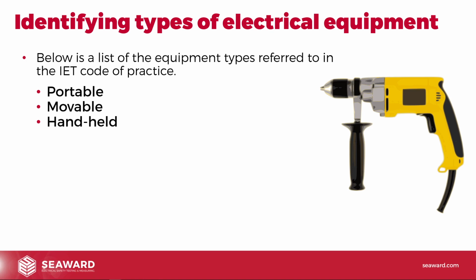Now, one that is seen as high risk, and a typical example here on the slide you can see the hand drill, is handheld equipment. Handheld equipment is really what you'd class as portable equipment, but handheld equipment is equipment that's designed to be held in your hand during normal use. Now, the problem with this is, where's it going to be when it goes wrong? In your hand. So the likelihood of somebody getting an electric shock if this piece of equipment goes wrong is a lot higher. Therefore, handheld equipment is generally seen as being higher risk.